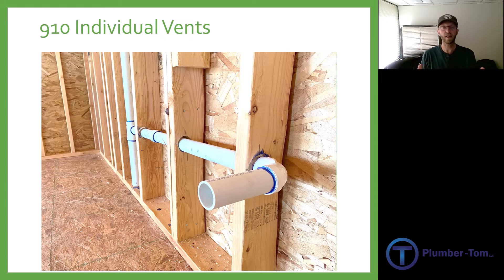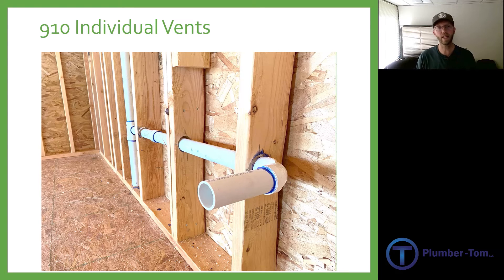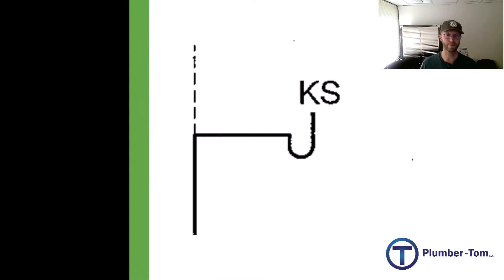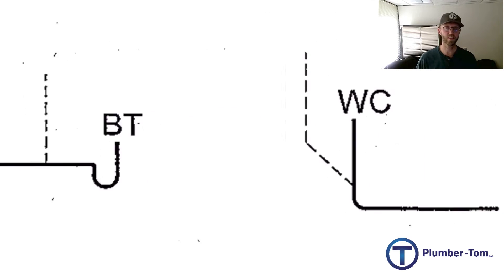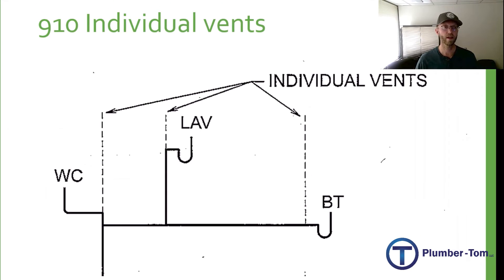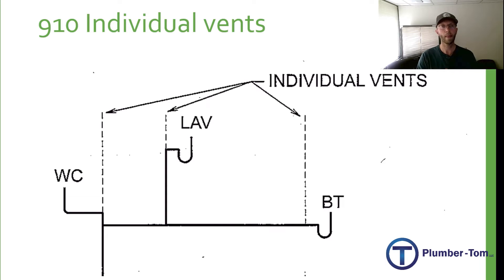Section 910 gives us our first and most reliable option for any venting, and that is the individual vent. There's not a lot to be said about this — there's only a very short paragraph in the code about this because it is so basic. It is that every trap receives its own vent. When you do it that way, there's plenty of pipe, plenty of air, and everything tends to flow pretty well. Here are some examples of individual vents in diagrams: a kitchen sink with an individual vent, a bathtub with an individual vent coming off the horizontal, a water closet with an individual vent, or a whole bathroom group with each fixture having its own vent. These individual vents work great, but they are time consuming and they cost a lot in materials by comparison.